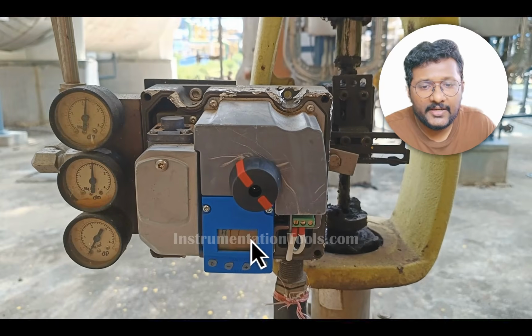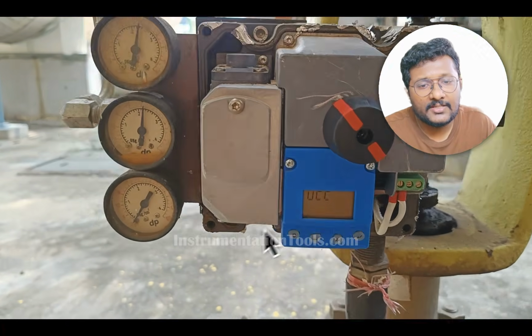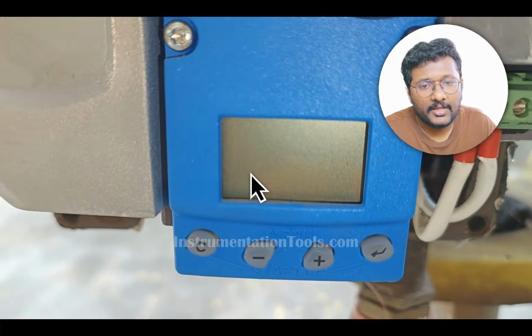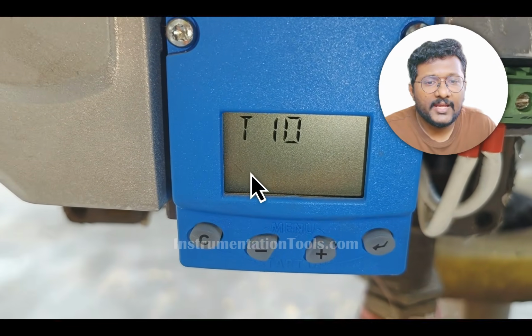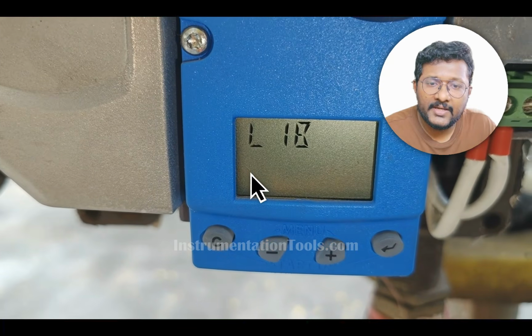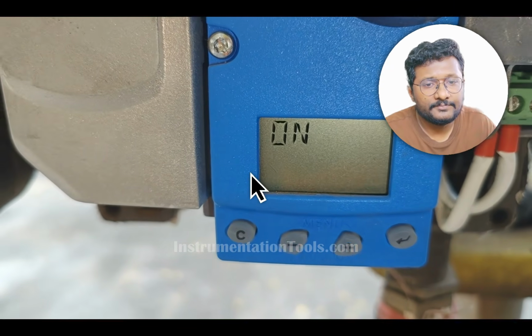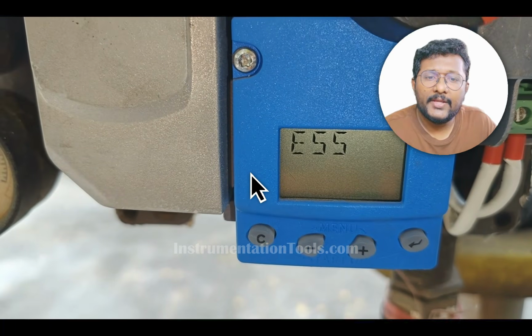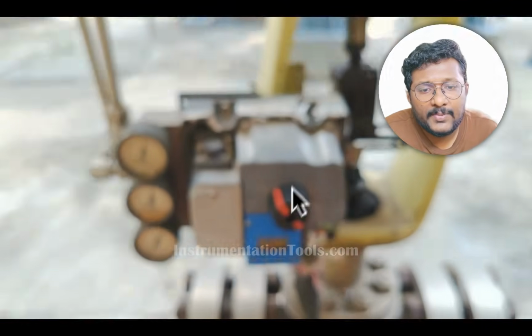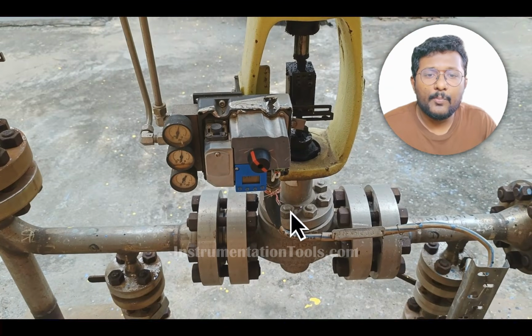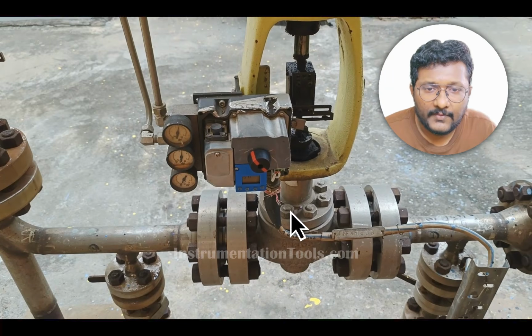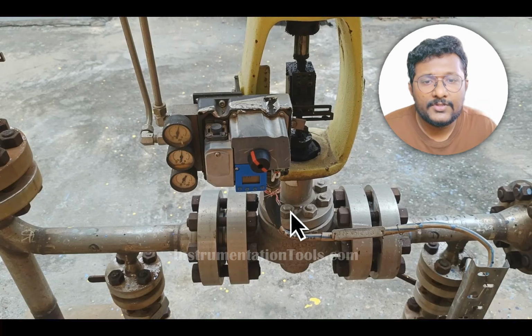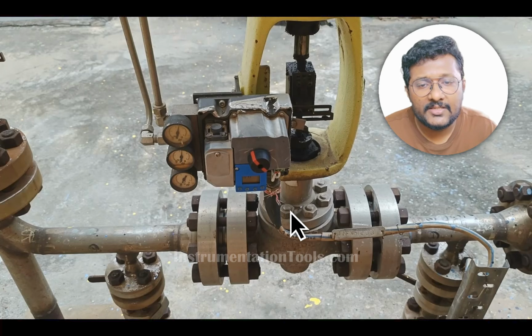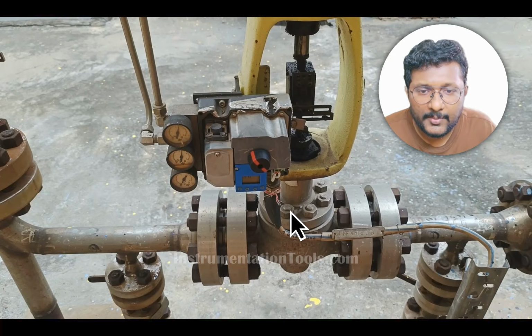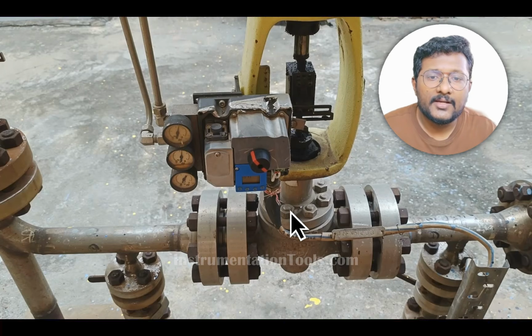The calibration is completed. You can see the message here, calibration successful. Okay. The calibration may take some time. Remember that it may take 2 to 5 minutes depending on your valve design. So by using this simple small display on the valve positioner, we can complete the calibration. Remember, if you need some advanced features, advanced diagnostic messages, then we have to use our HART communicator. For normal maintenance purpose, we can use this display.